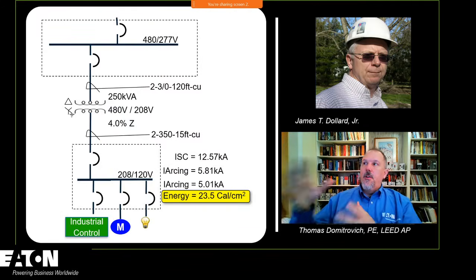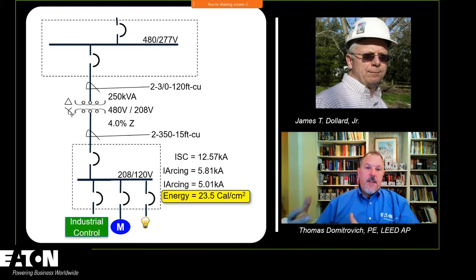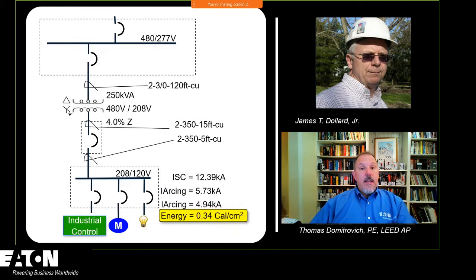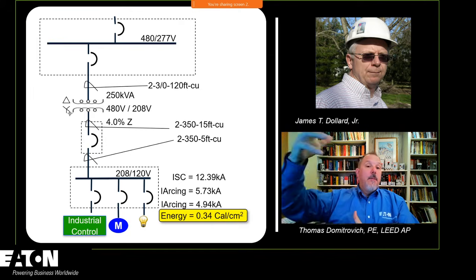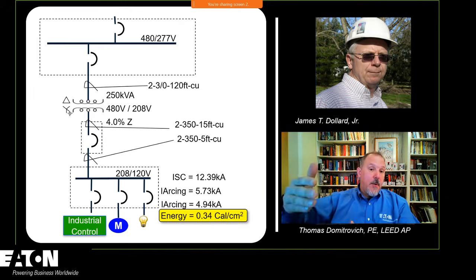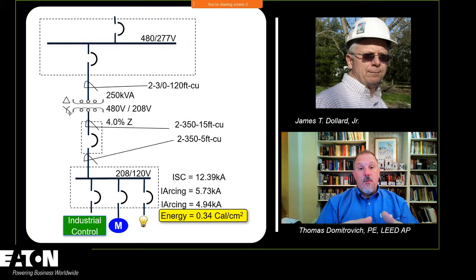When you look, and we talked about this from a transformer perspective, that secondary panel board off of a transformer being one that's got a lot of incident energy. Like in this case here, I've got a 250 kVA transformer, and my incident energy is 23.5 calories per centimeter squared. I could redesign that system, move that circuit breaker out. Now I can take credit for that main overcurrent device because it's now in a separate enclosure. I don't have to worry about line side propagation. The incident energy in that piece of equipment that I would get into probably a lot more frequently than anything else, I've now reduced down to 0.34 calories.